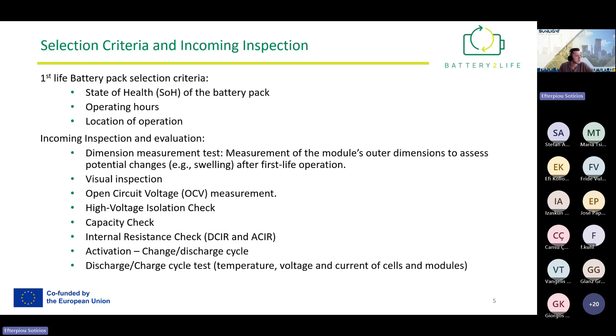After that, we have electrical tests: open circuit voltage measurement to ensure it is within limits, high voltage isolation check to ensure there's no isolation problem, capacity check to see if it fits our application, and internal resistance check. Then we activate the battery by charging and discharging it for one cycle. We also measure the temperature, voltage, and current of the cells and modules.